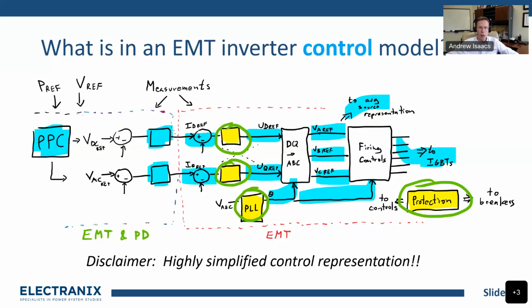These things are proprietary and specific. These phase lock loops are proprietary and specific. These are actually the secret sauce of a lot of these inverter manufacturers. They will never tell you how they work, but the way that they work will determine whether or not finally you'll have protection operation either in the controls or off to the breakers and trip the plant. So all of this excitement happens in here after a fault clears, for example.